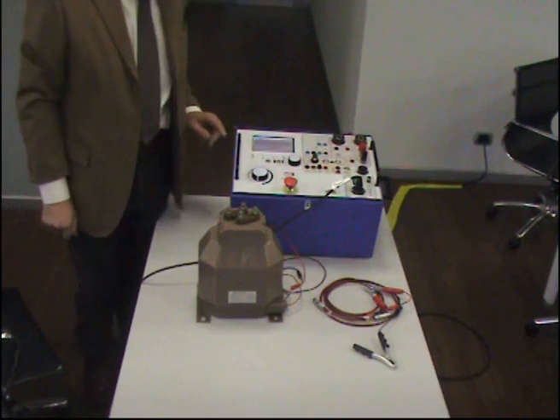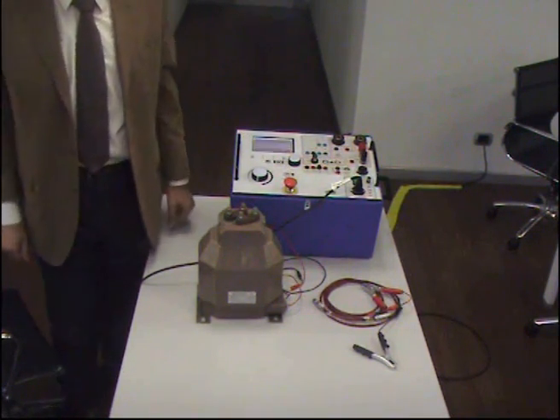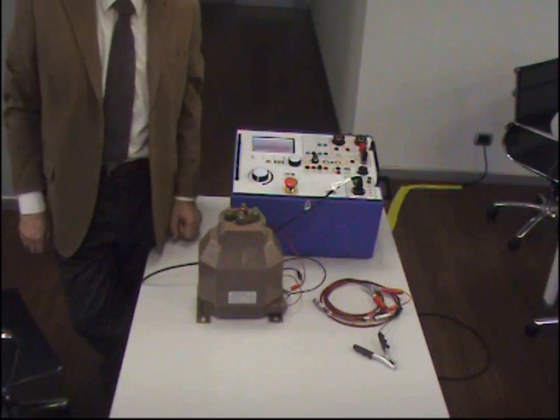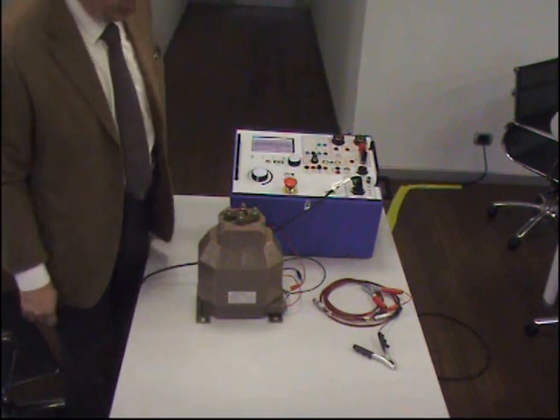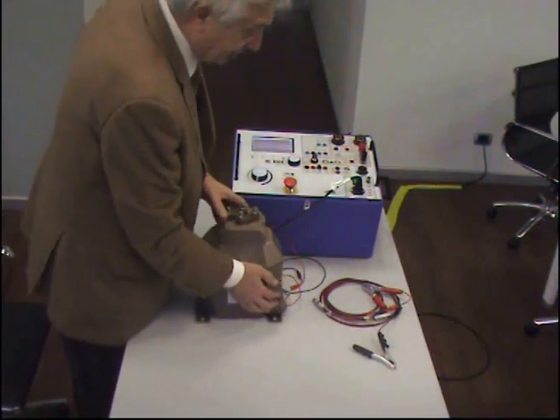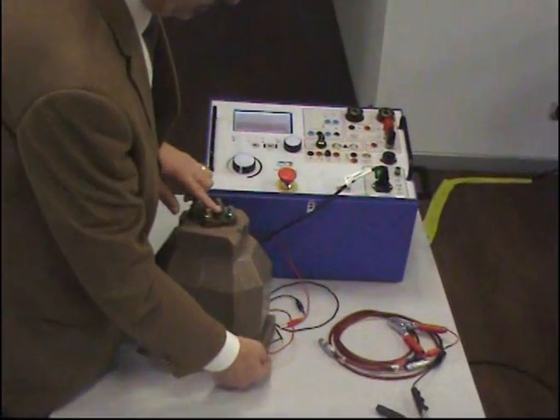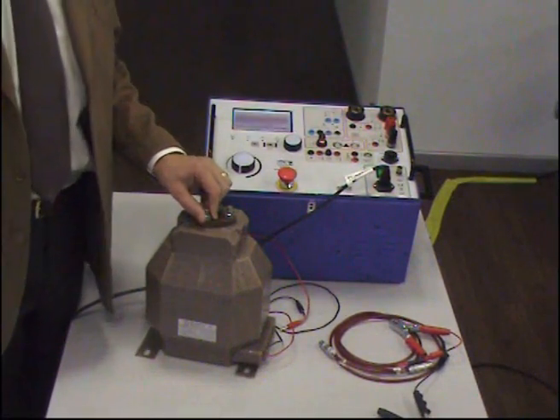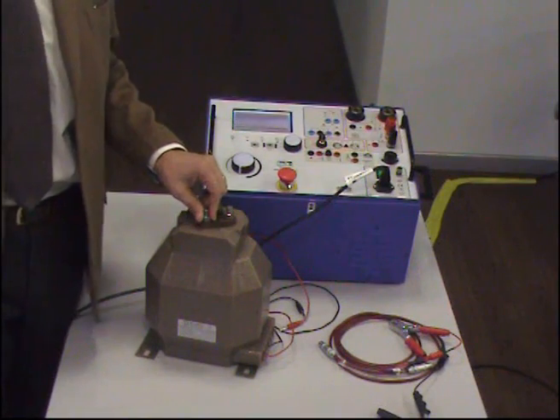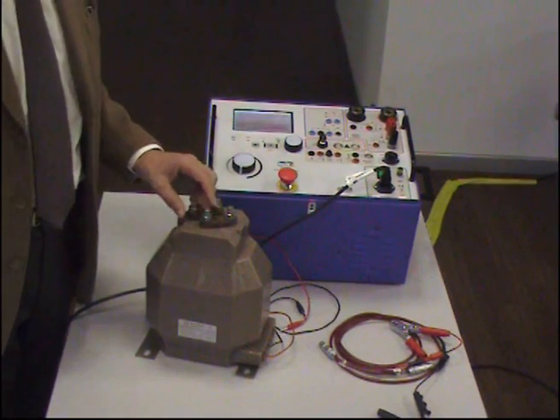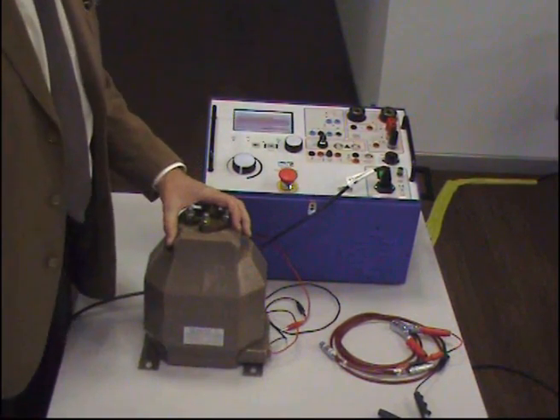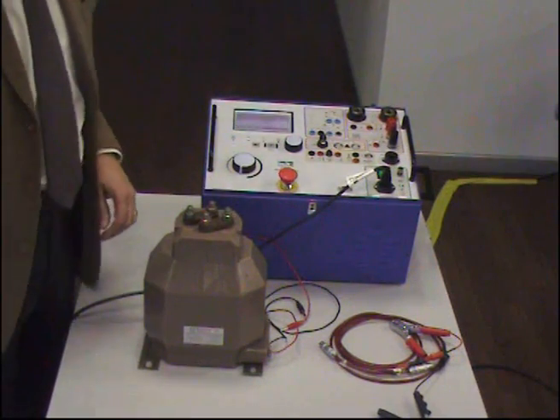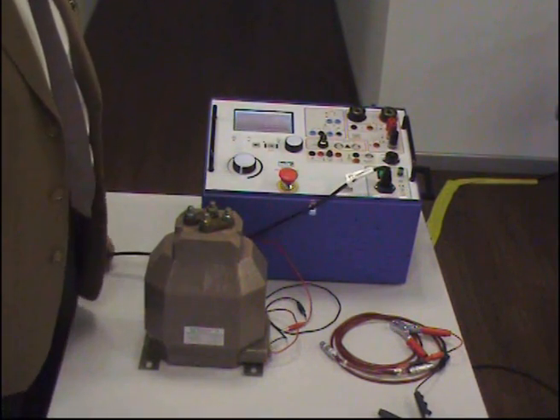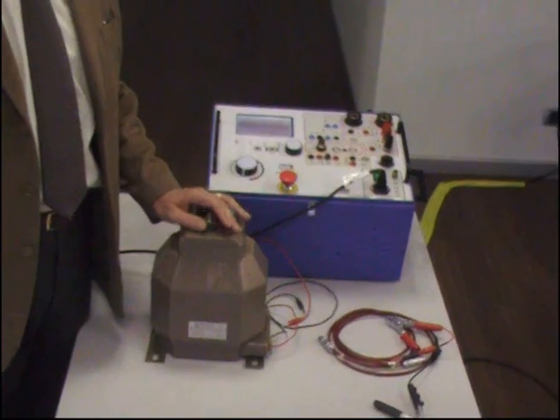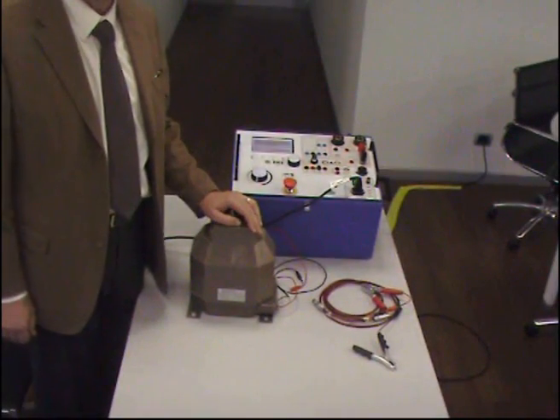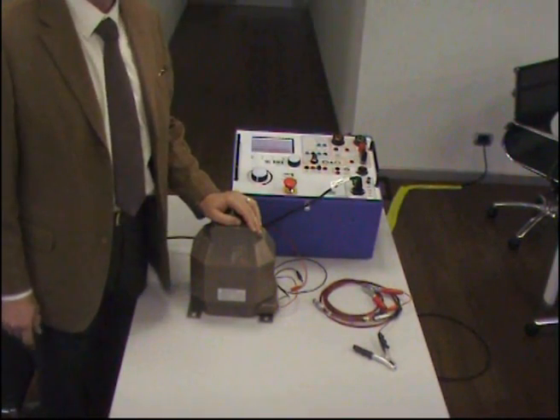Next test is the voltage withstand test. Of course, this voltage withstand test does not apply at the test between primary and secondary side, because there we would need 15,000, 30,000, I don't know how many kilovolts. But it is absolutely important and mandatory to perform the test of the isolation between the secondary side of the current transformer and the ground.